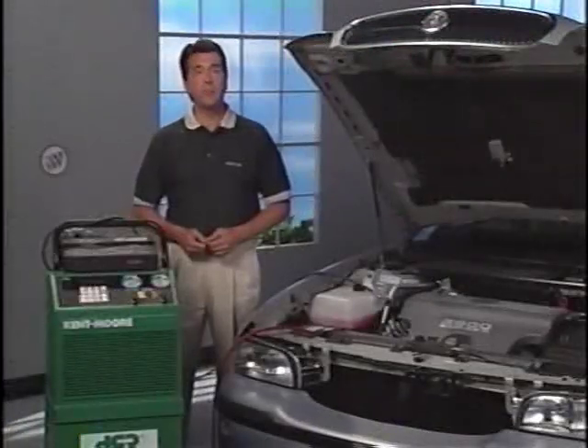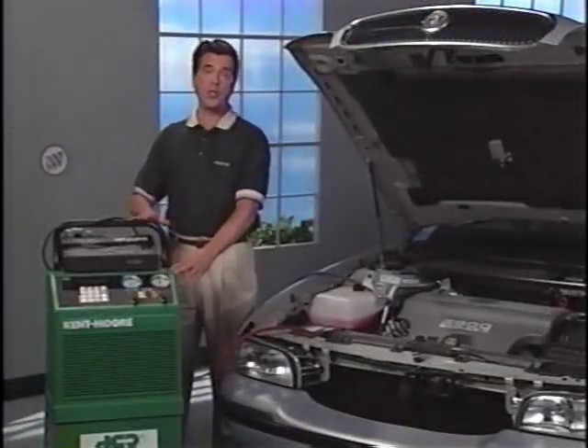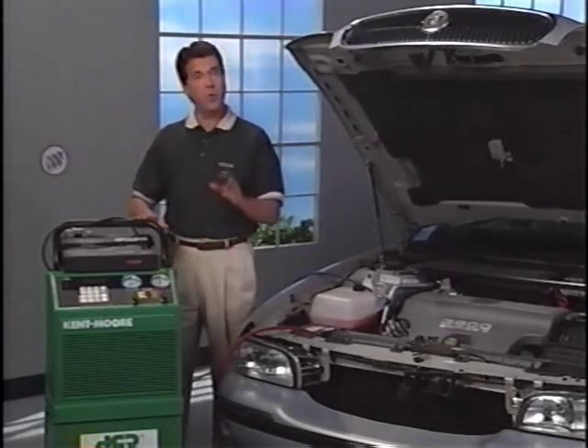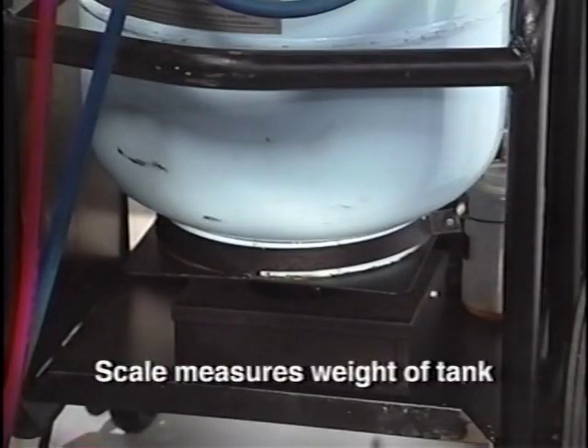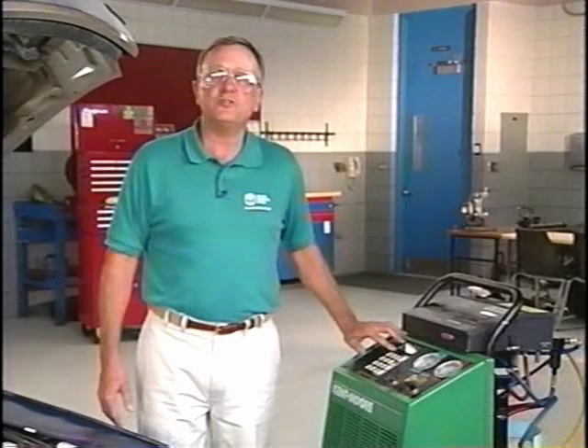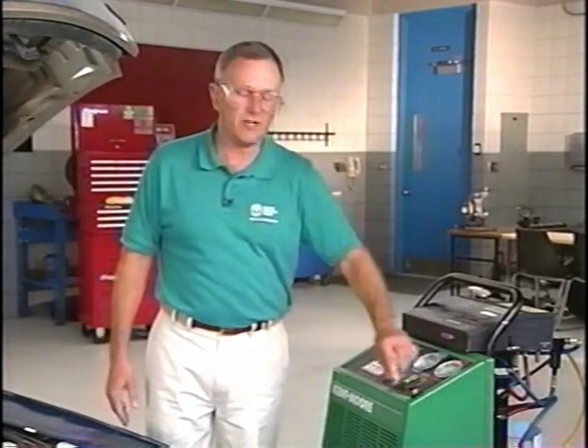Be careful not to bump the ACR4 while the charging process is going on. Remember, the ACR4 measures the charge by measuring the weight of the tank. If the tank moves, the measurements mean nothing. When the display shows complete, close the high side valve. Now both the high and the low side valves are closed.